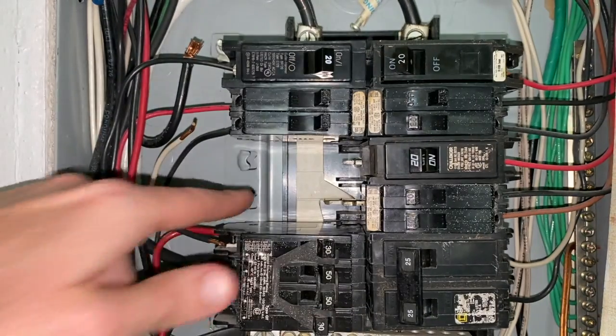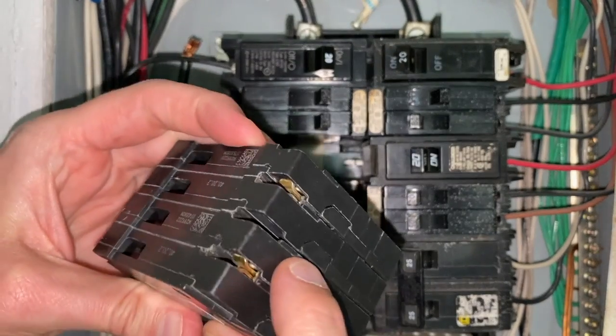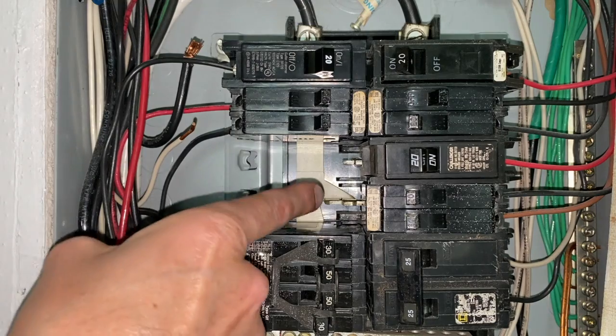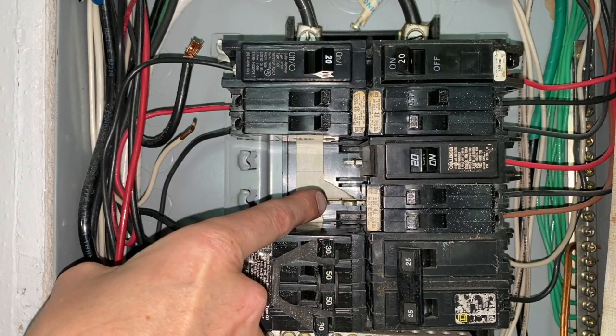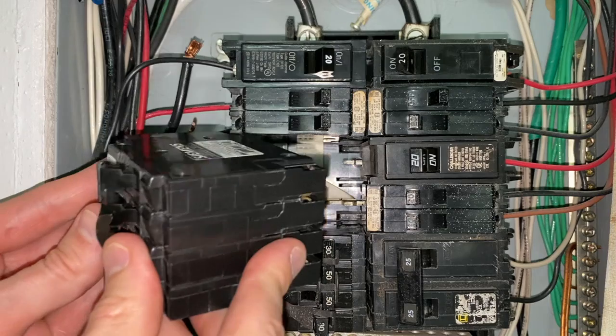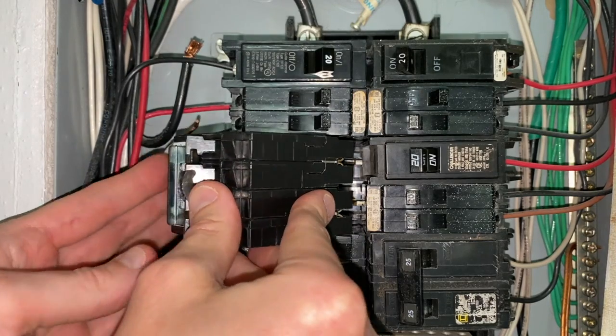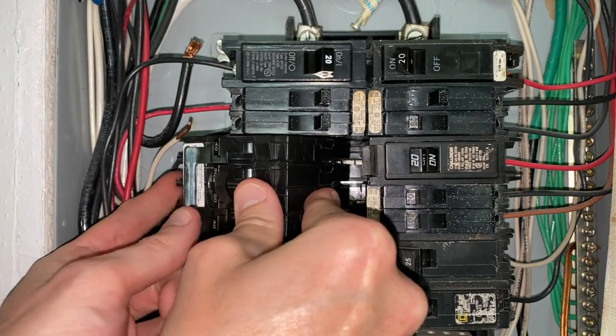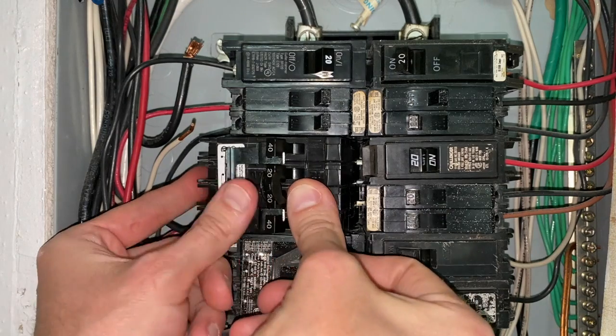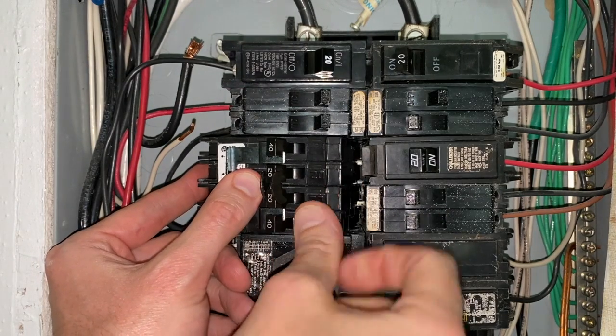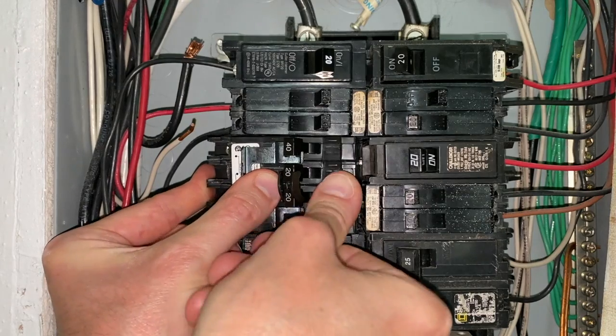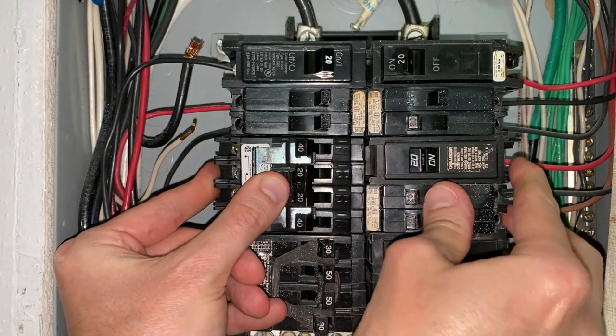Back to the panel and referencing those 2 inner hooks, and again, that is what this portion of the new breaker will secure into. And then the opposite end, where the electrical contacts are, will slide in and make contact with the inner contacts there. And go slow, be precise, do not force anything, come in at an angle, and again we are looping those inner hooks inside those braces, and once you're in, just carefully slide it and connect the electrical contacts. And that's a lot more firmer, and I like it.